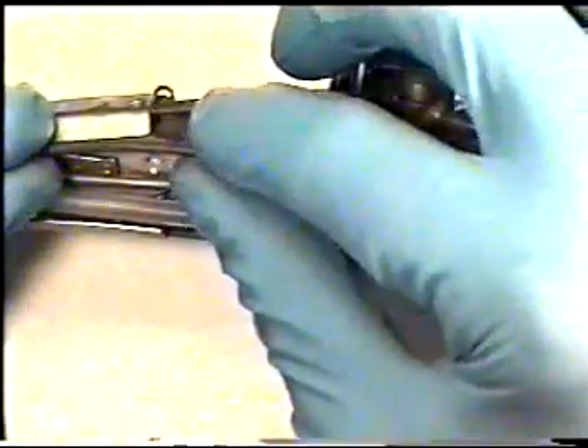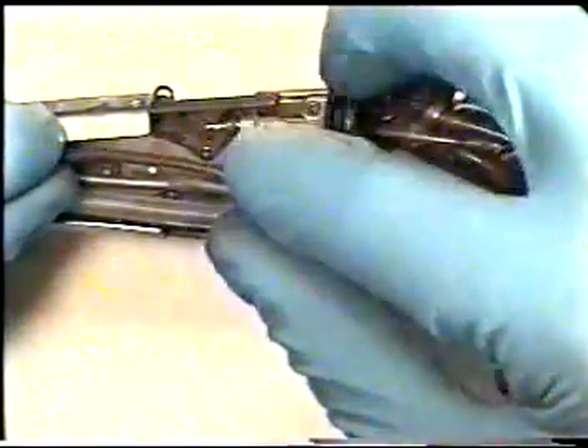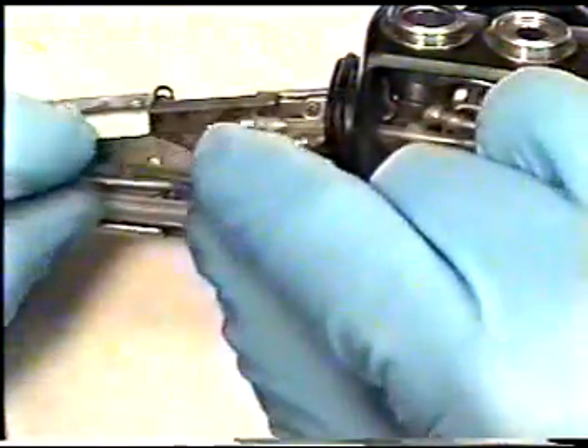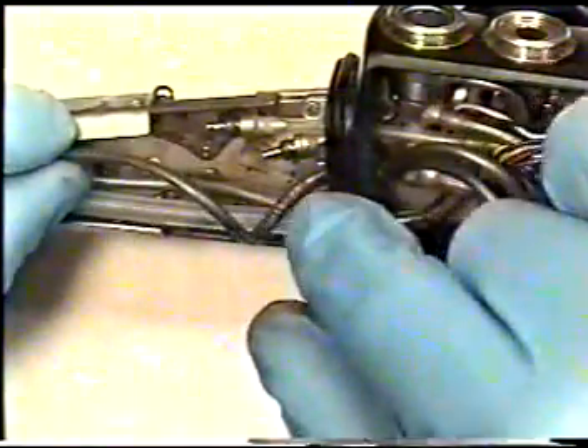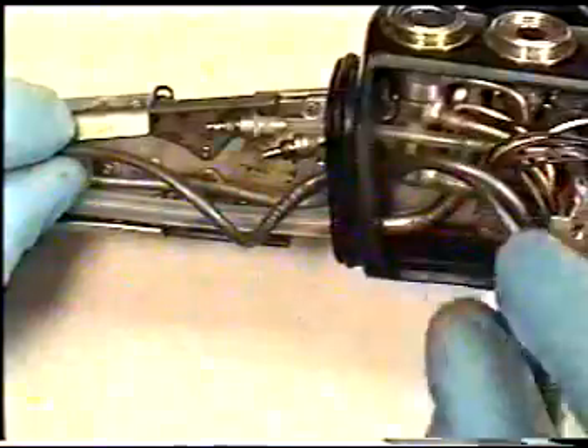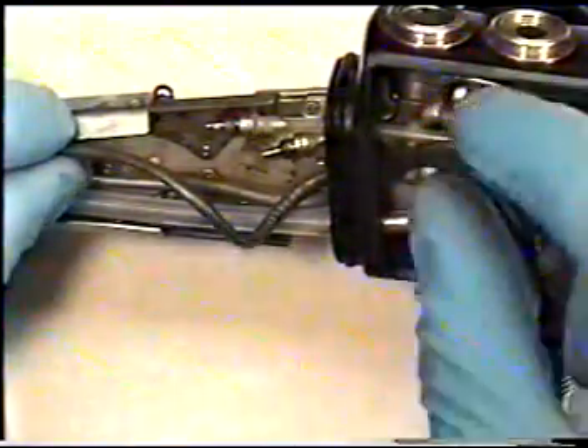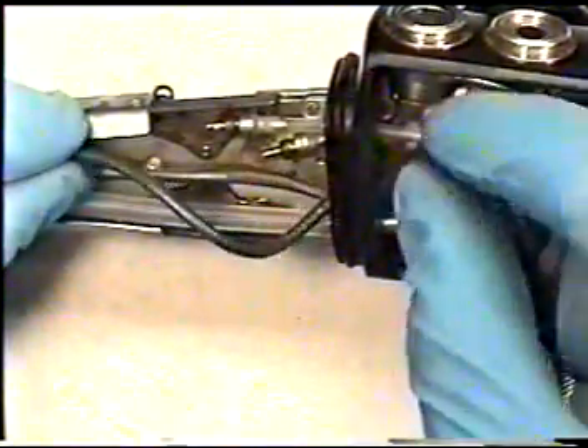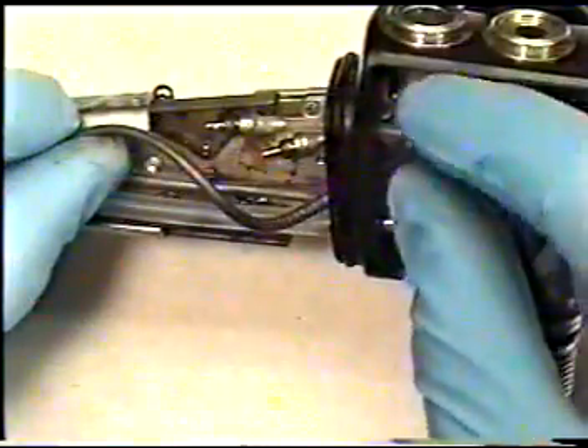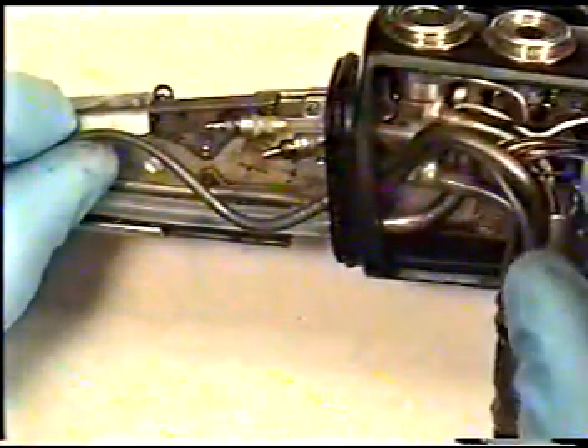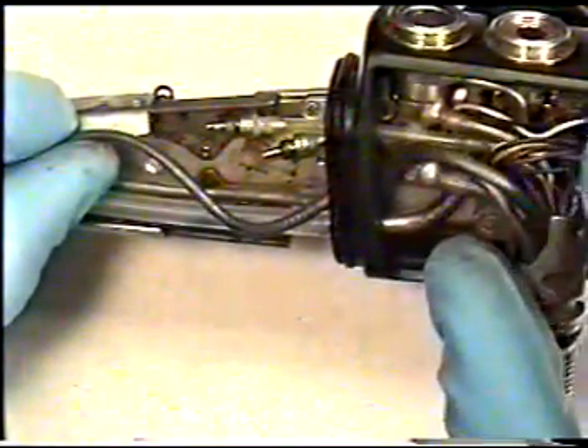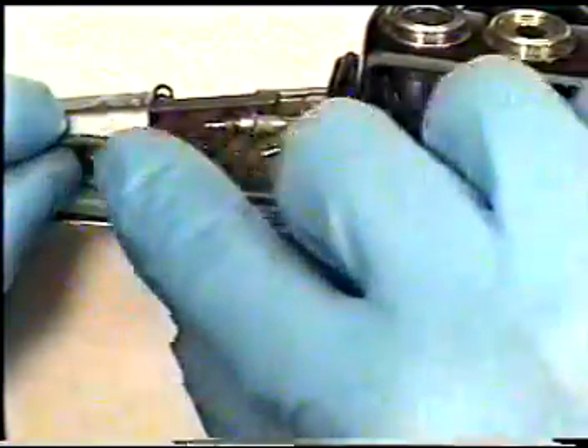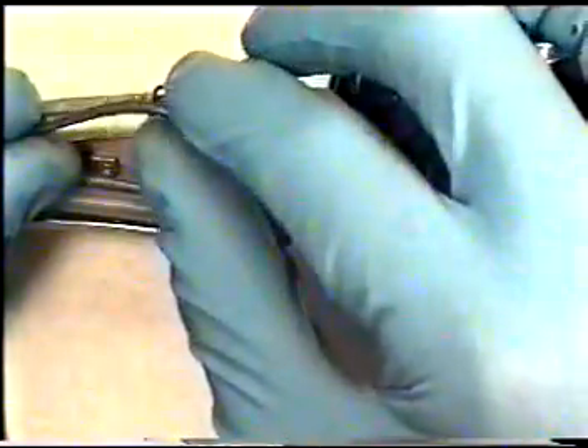Again, be very careful that you are not grabbing your image guide, which you can follow by being sure the light guides are coming from out of the umbilical light guide tube. These are the two tubes that we will pull through the insertion tube and body section, and not the image bundle which runs from the eyepiece through the body down into the insertion tube. Again, be very sure you are pulling on the light guides.